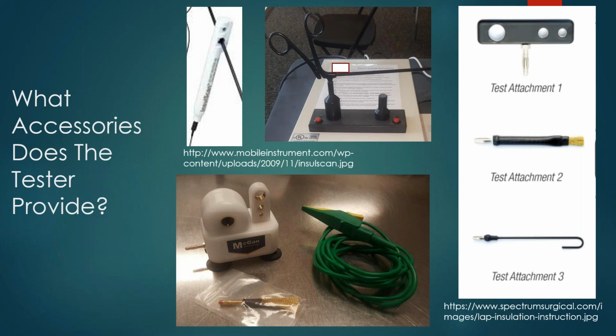I've seen the brush on test attachment 2 completely worn down, where you really can't use it. On the bottom there, where you see a fixed block with the round piece, which we'll go into, it's basically damaged on the outside from being dropped. Or the most damage I see throughout is going to be your grounding wire or your attachment, where I'm seeing technicians tape it, which is very, very unsafe, and you do not want to do that. So again, just some examples of that.